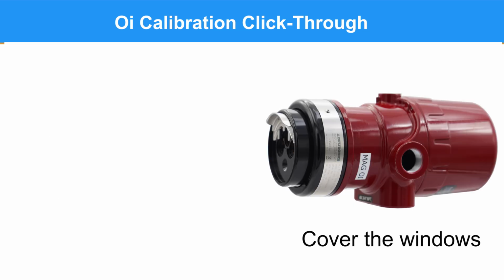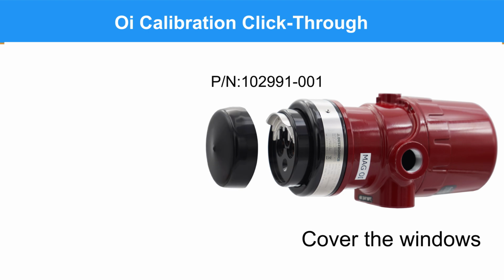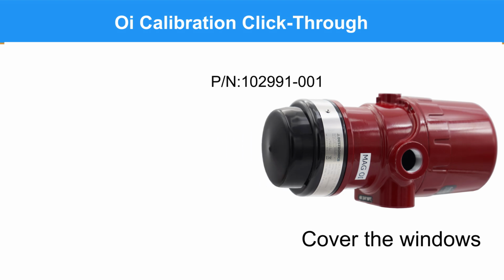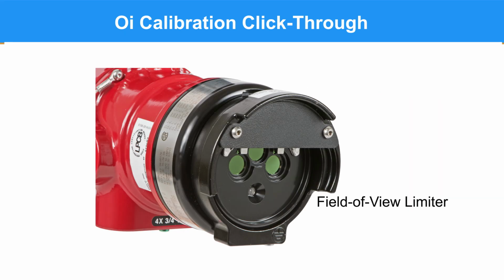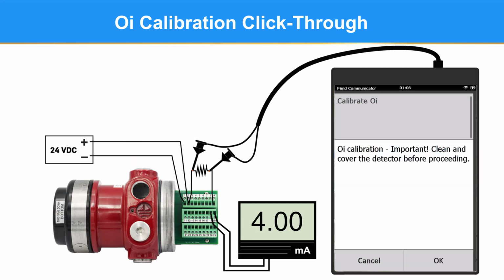You then need to install the cover to make sure no IR energy is affecting the OI calibration. For those detectors with field of view limiters, the black cap does not fit over the field of view limiter, so the limiter must be removed before the cap can be installed. If the limiter can't be removed, a suitable IR blocking enclosure must be used to block the windows from any outside IR energy. After all 6 windows have been cleaned and the cover installed, select OK.